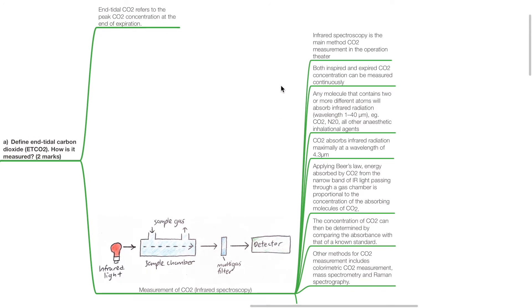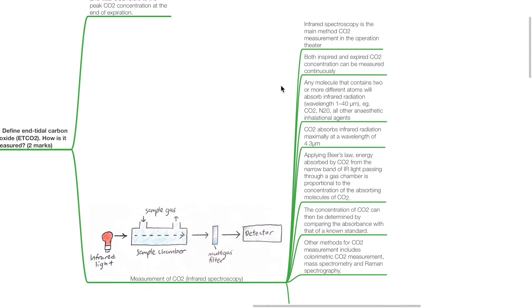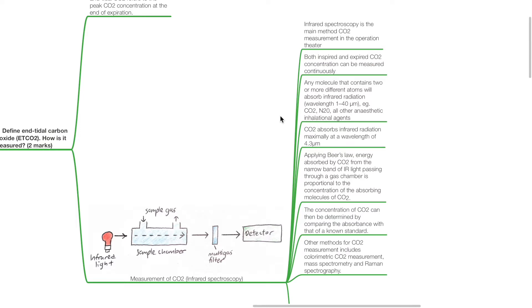Both inspired and expired CO2 concentrations can be measured continuously. Any molecule that contains two or more different atoms will absorb infrared radiation, for example CO2, nitrous oxide, and all other anaesthetic inhalational agents. CO2 absorbs infrared radiation maximally at a wavelength of 4.3 micrometers. Applying Beer's Law, energy absorbed by CO2 from the narrow band of infrared light passing through a gas chamber is proportional to the concentration of the absorbing molecules of CO2.